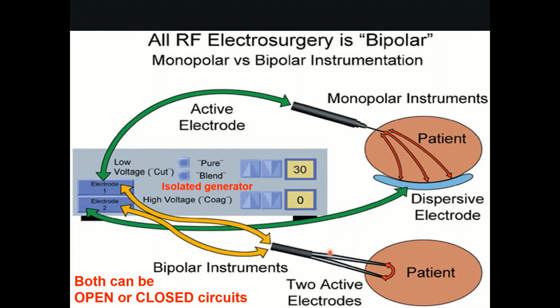Agreed? Now, there's another term which you should know about the electrosurgical unit and the application of electrosurgery to the human body, and that is open or closed circuits. What is an open or closed circuit? If the electrode is touching your body, it is a closed circuit. But there could be an instance where the electrode stops short, I'll show you in a future slide, and the current has to pass through some amount of air to reach the body. That is an open circuit, right? Open, because there's a gap between the tip of the electrode and the patient.